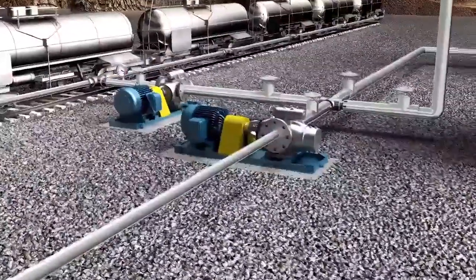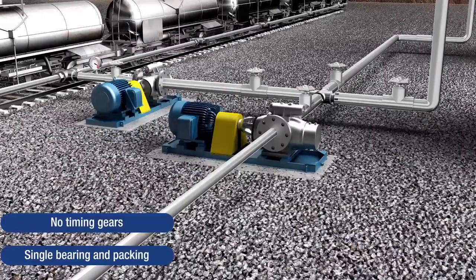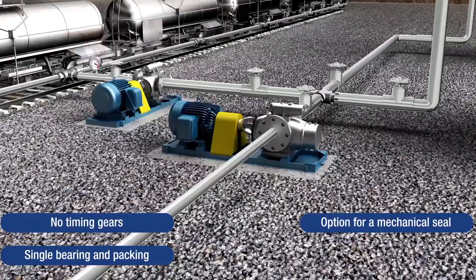Leistritz's L2 pump is a twin screw pump with no timing gears. It has a single bearing and packing, with an option for a mechanical seal. Pumps operate at synchronous speeds, eliminating the need for gearboxes.